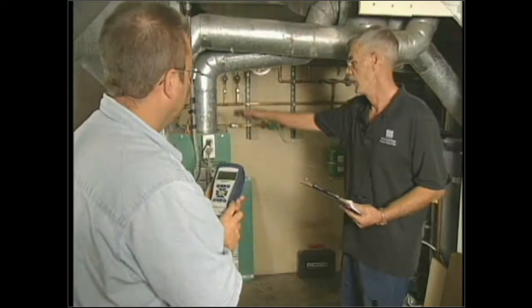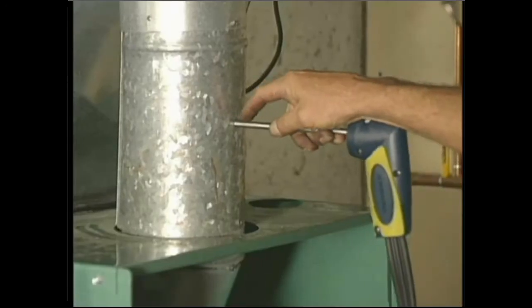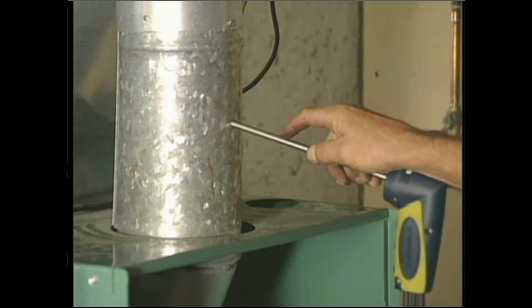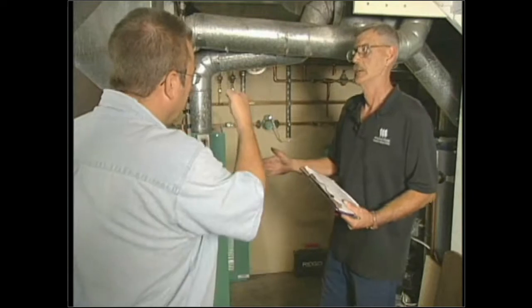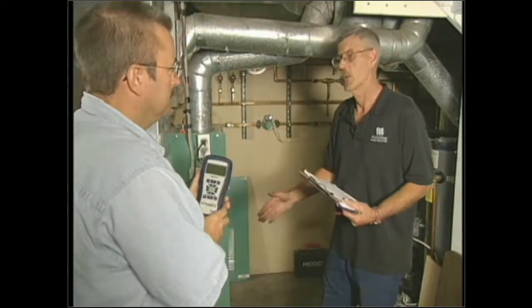Then the next thing we do is we go to the same hole where we took our draft and our smoke. We slide our probe in, go all the way to the back, and then we bring it back so it's dead center. We want to measure that core. That's really the key for the auditors. Make sure you have the probe in the center of the flue.